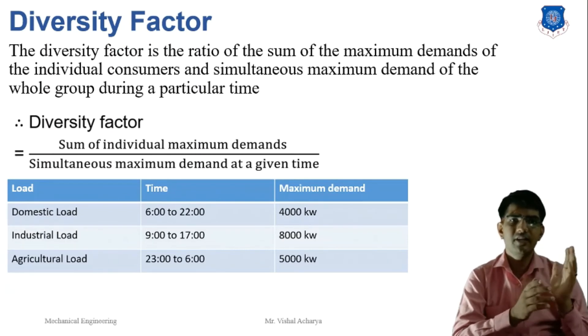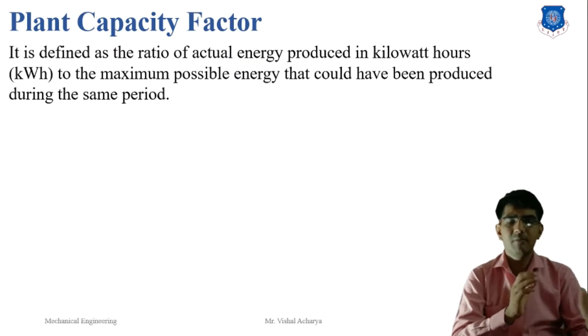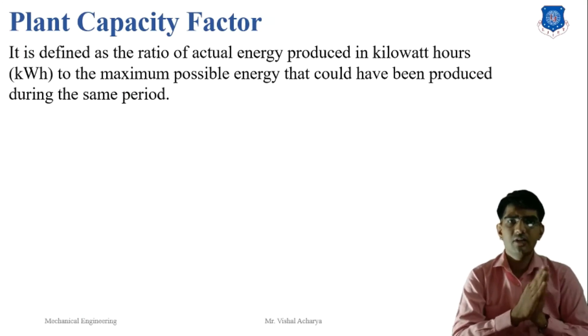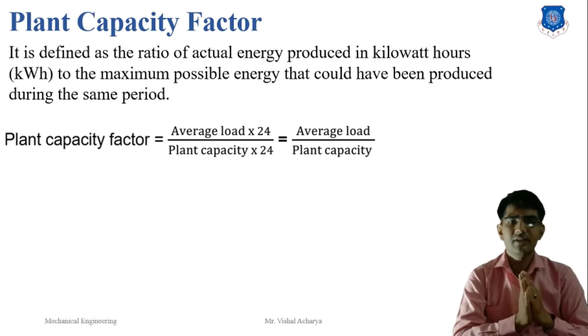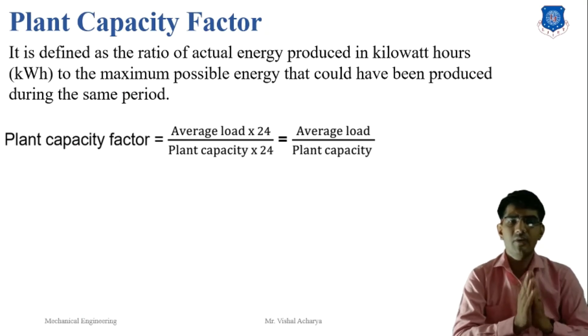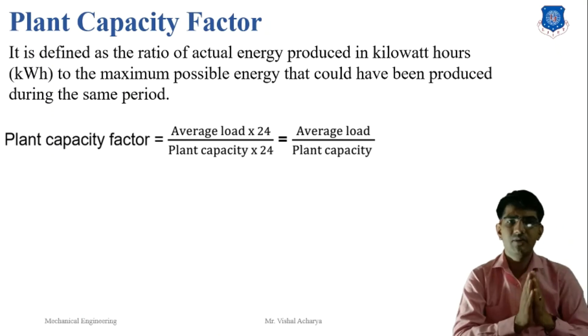Diversity factor is always greater than 1 because the sum of individual maximum demands does not match the simultaneous demand at any given time. The next term is the plant capacity factor. It is defined as the ratio of the actual energy produced to the maximum possible energy that could have been produced during the same period. Plant capacity factor = average load / plant capacity. If plant capacity is 500 MW and average load is 300 MW, then plant capacity factor = 300 / 500 = 0.6.